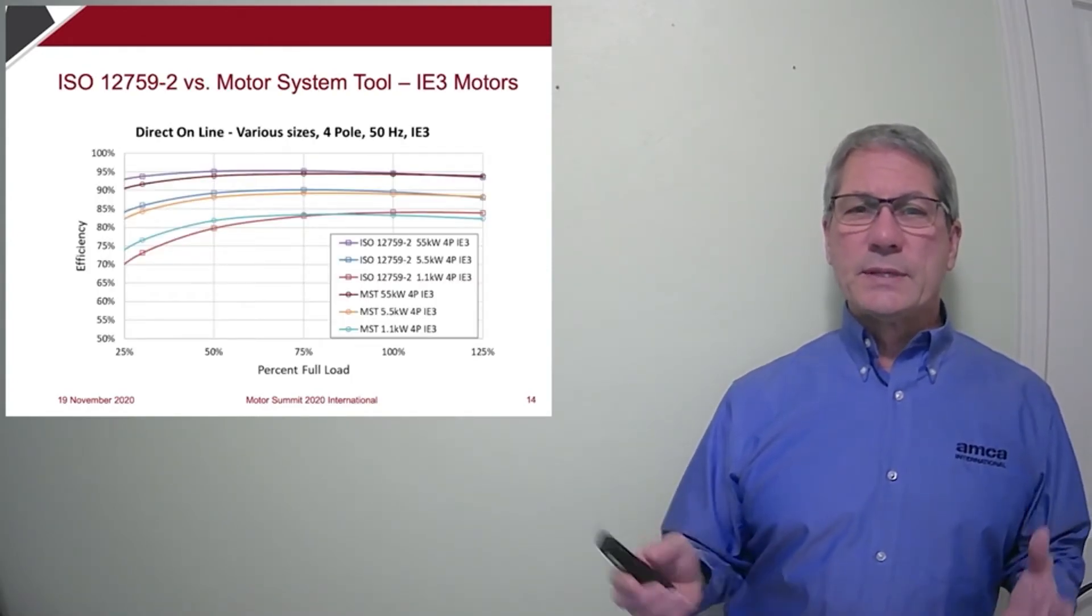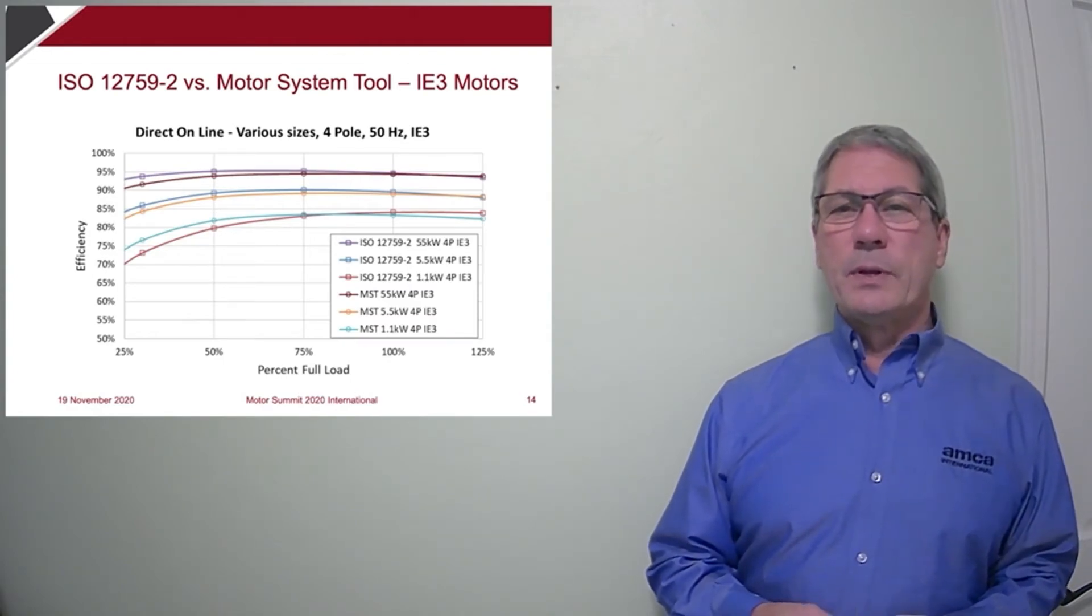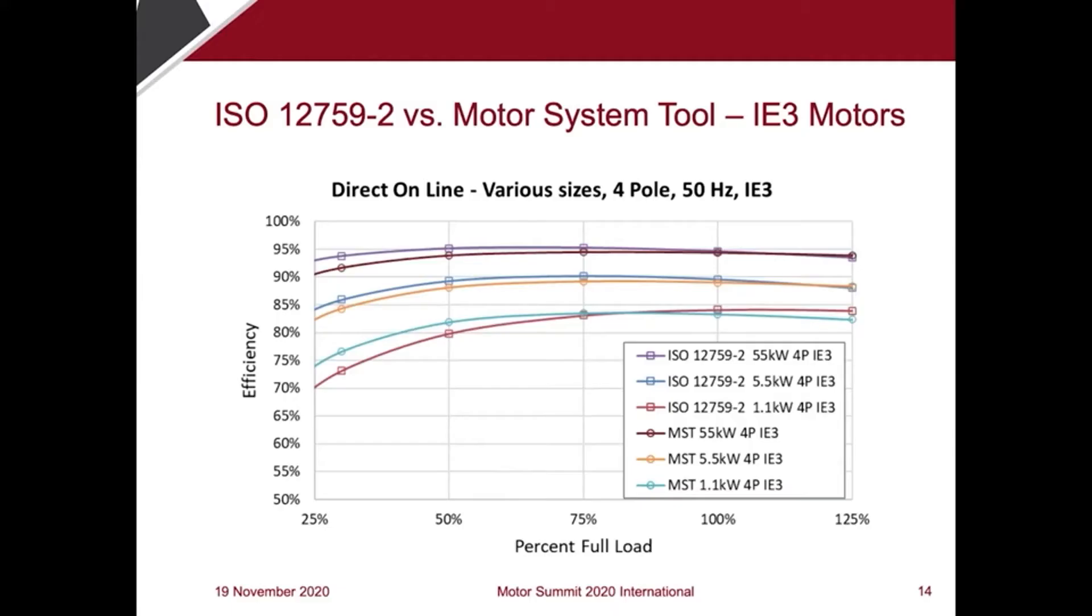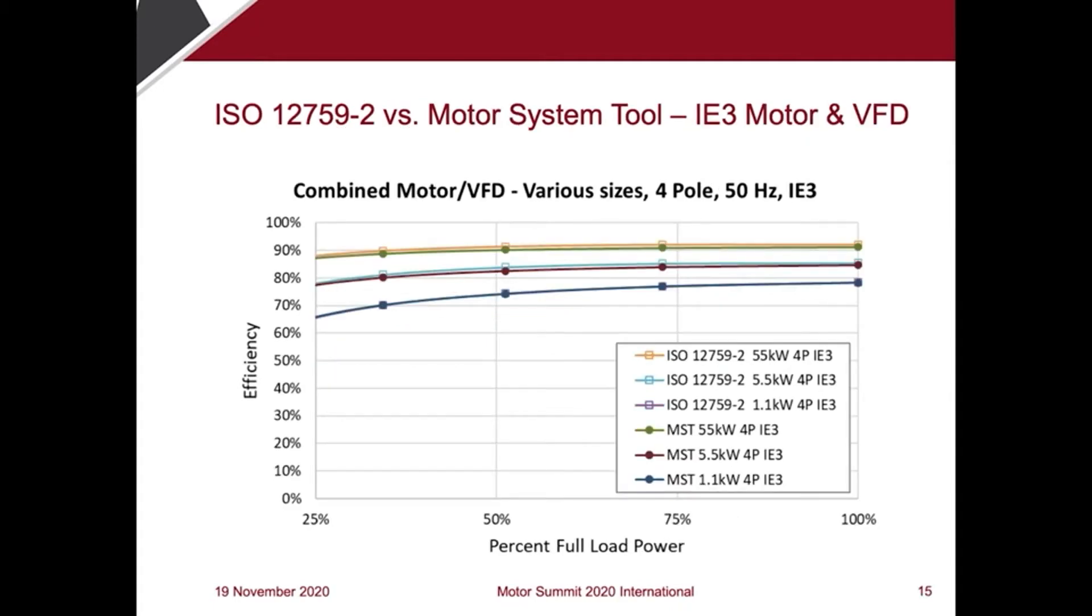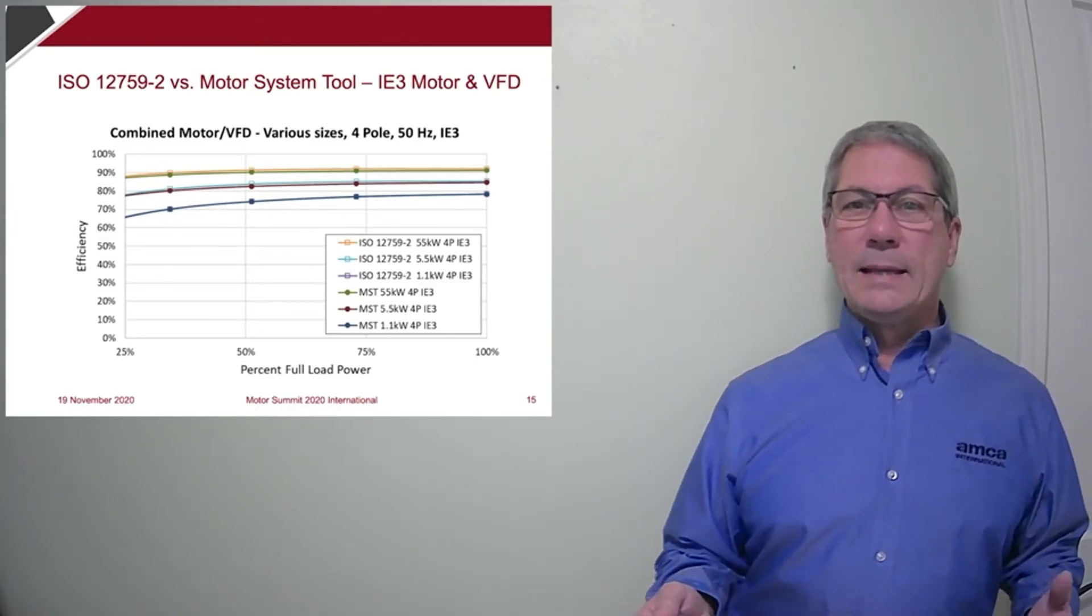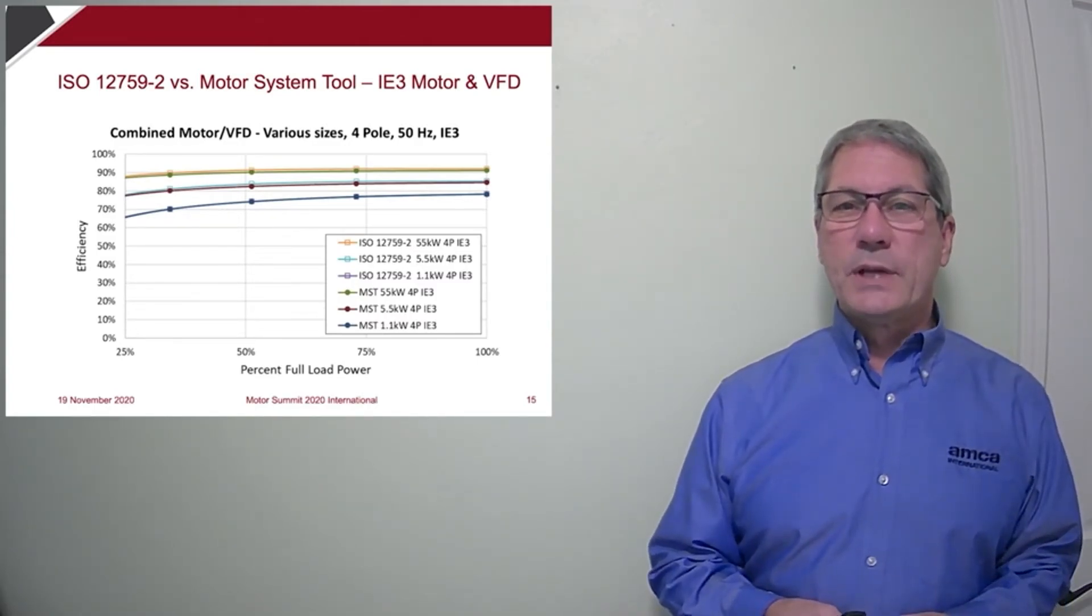So how did we do with this standard? Well, we have extremely close agreement with the efficiencies published by the Motor Systems Tool, a very useful tool put out by EMSA. Here I have shown three different size IE3 motors with part load efficiency values, and you can see the correlation is excellent. And here's the comparison for IE3 motors combined with VFDs. Again, almost an exact match.